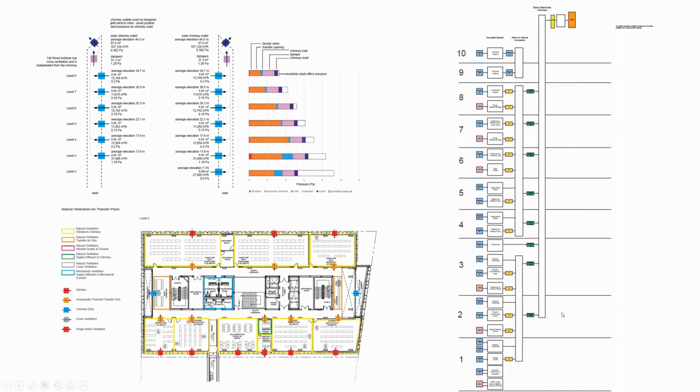In this project, because of the modular design — each floor has its own air handling units — and each space has VAV diffusers controlled by individual CO2 sensors, if any one space decides it doesn't want to be in natural ventilation mode, it doesn't impact other spaces. They can close their windows and run with mechanical ventilation while the other spaces continue in natural ventilation mode with no impact. It's really flexible that way.